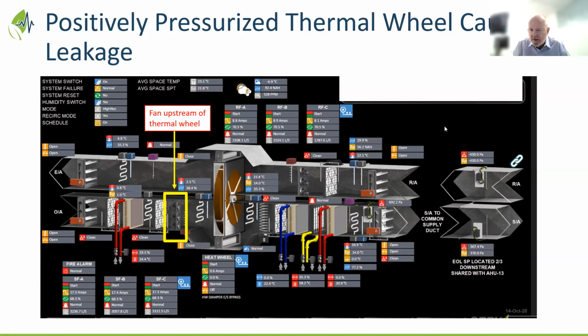Is there an indicator? There's no indicator. I think that will be confirmed through their testing. It could be confirmed through a smoke test to see the flow of the movement of the purge. But that's generally done through testing performed by the TAB contractor to confirm that it's in the right direction and there's no cross contamination happening.